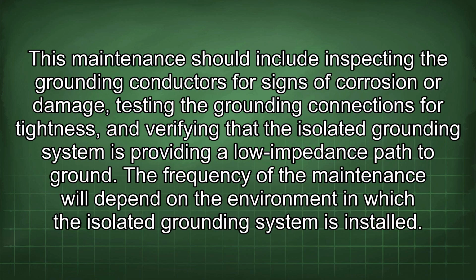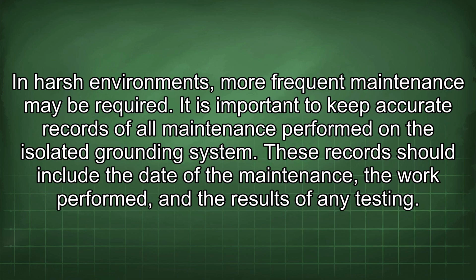This maintenance should include inspecting the grounding conductors for signs of corrosion or damage, testing the grounding connections for tightness, and verifying that the isolated grounding system is providing a low impedance path to ground. The frequency of the maintenance will depend on the environment in which the isolated grounding system is installed. In harsh environments, more frequent maintenance may be required.